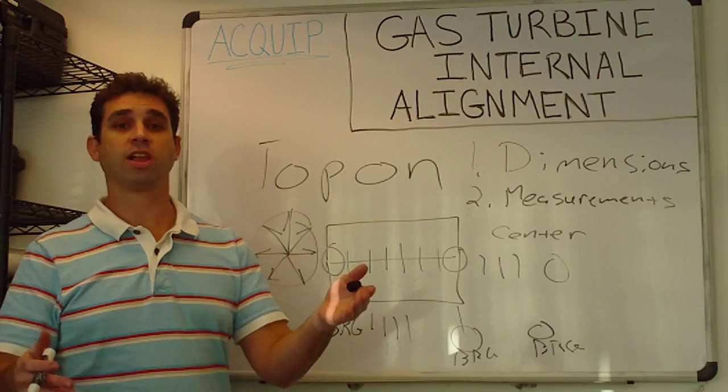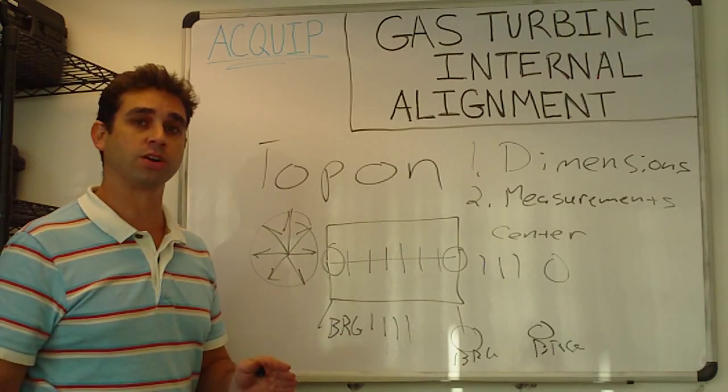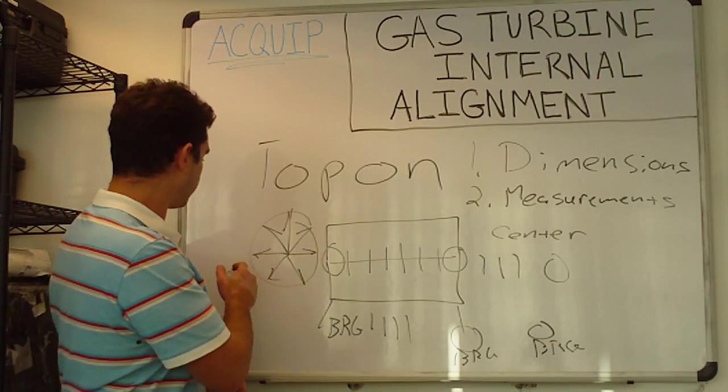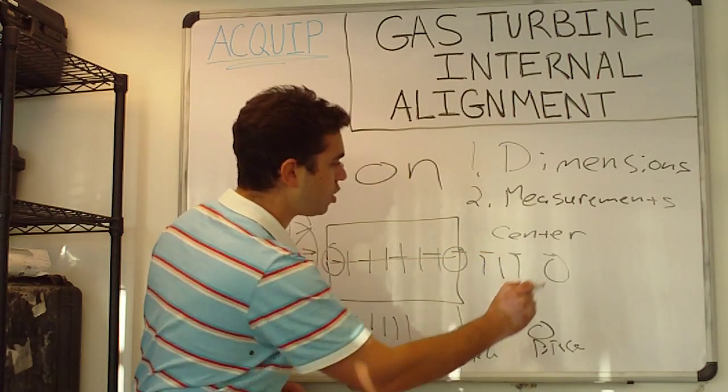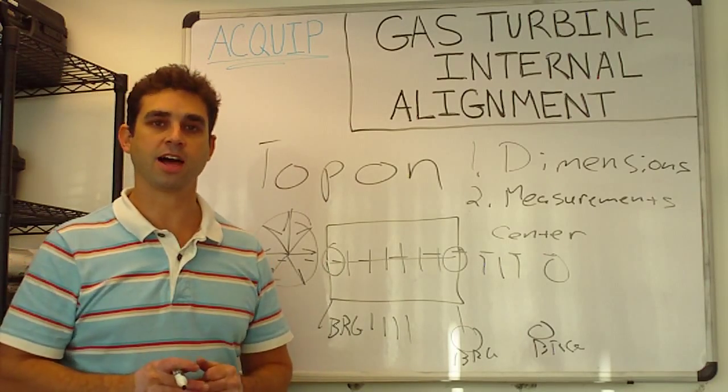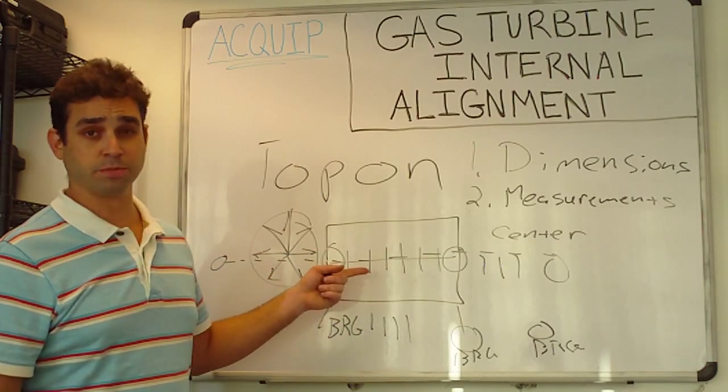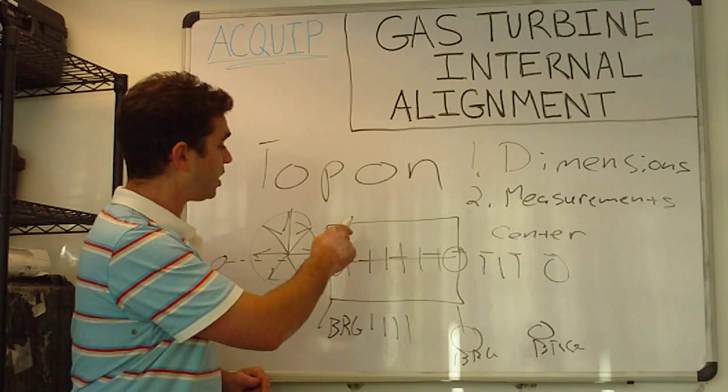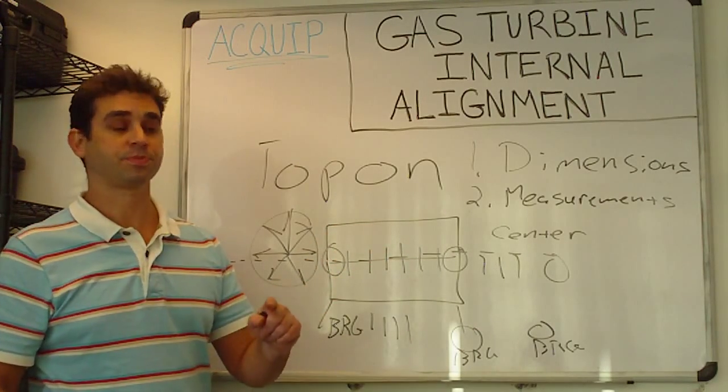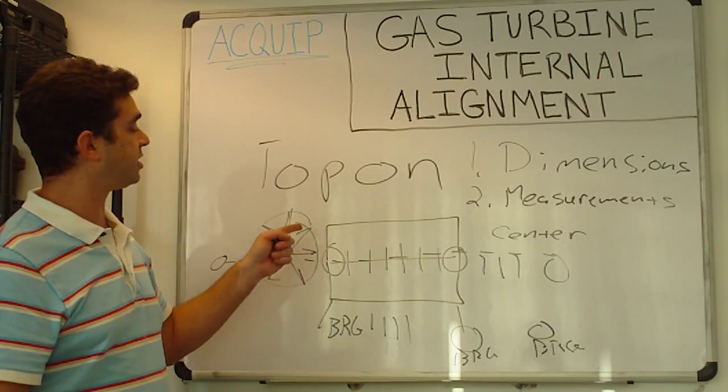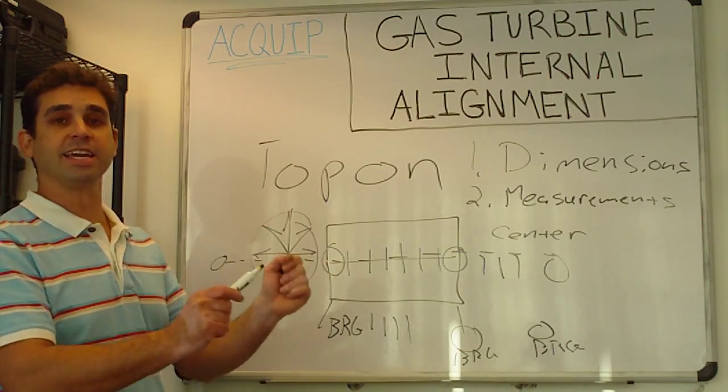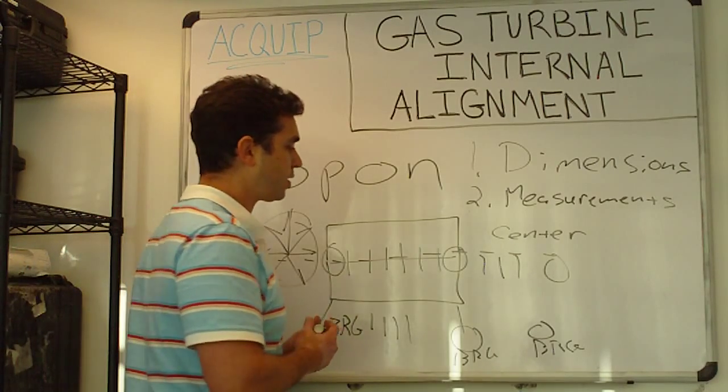We usually do laser alignment when we do a gas turbine internal alignment. And so what we'll do is we'll set a laser up and shoot the laser through the turbine and that'll be our reference line. It'll act as a datum and then we'll measure each one of these bores. We'll know the center of each bore and they'll be related to the laser so that each bore can be tied together inside of our data.